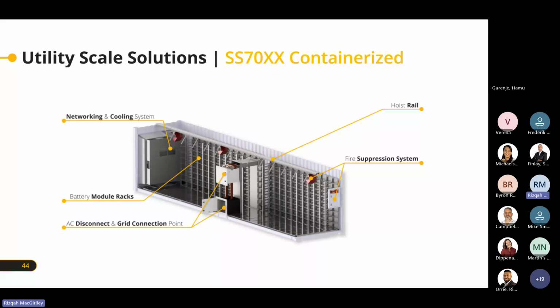We also have our networking and cooling system, which contains two 36,000 BTU fans, a Logger V2, and a built-in UPS system. Should there be no power, the UPS will start up and power the communications. All the communications are at the back of the container, and the entire container is designed for external access, because as far as possible we don't want anyone inside it, as it is quite dangerous. In the event of a fire, we also have a fire suppression system.